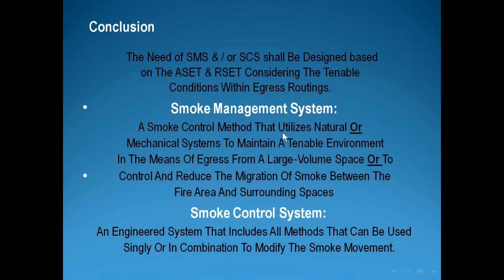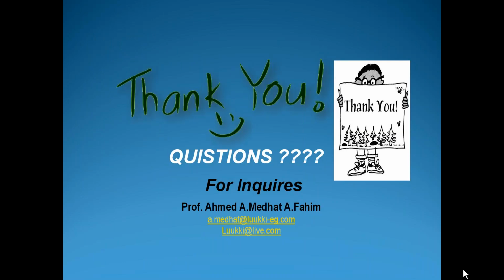Smoke management is a smoke control method that utilizes natural or mechanical systems to maintain a tenable environment in the means of egress from a large volume space, or to control and reduce the migration of smoke between the fire area and surrounding spaces. While the smoke control system is an engineered system, a system designed, okay, that includes all methods and ways that can be used singly. If you have an open atrium inside a building, we can use it for natural smoke extraction, singly or in combination, to modify the smoke movement, to control the smoke movement in a certain way and design my egress routing in another way, so you protect your people from the hazard of smoke. Thank you very much for your listening.